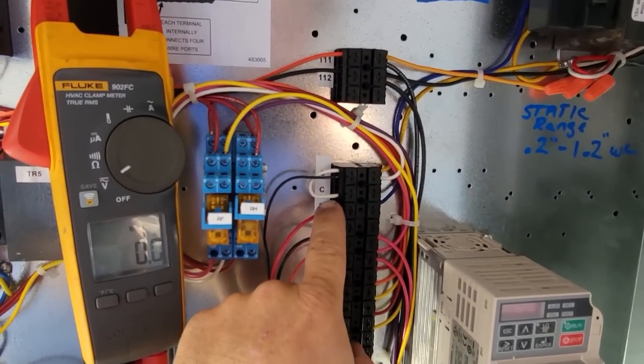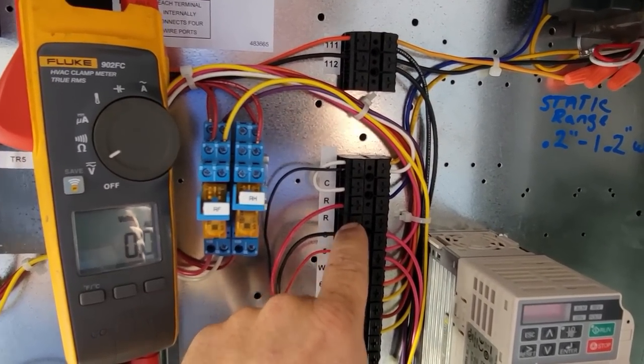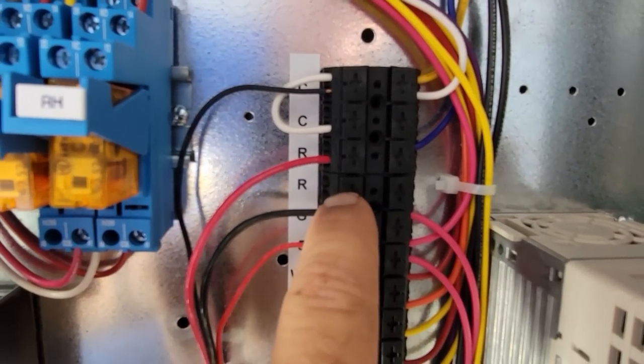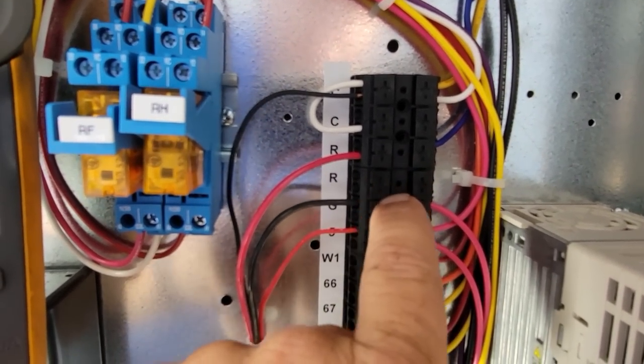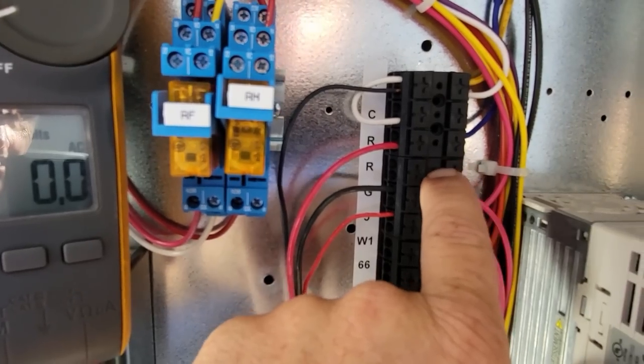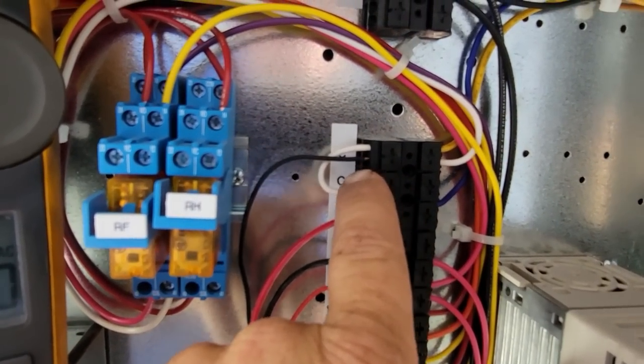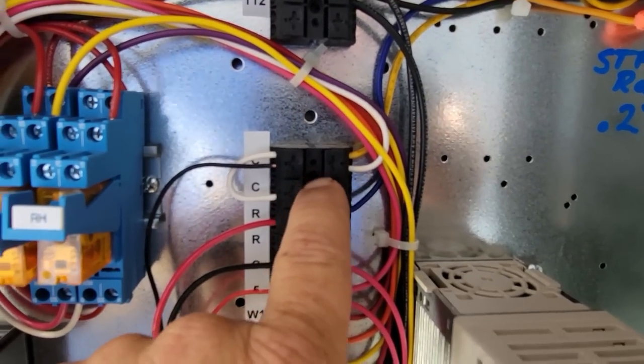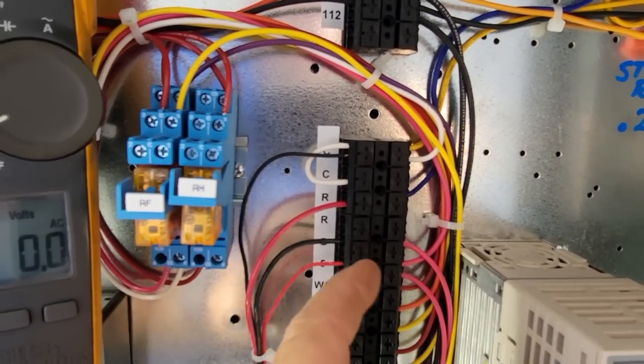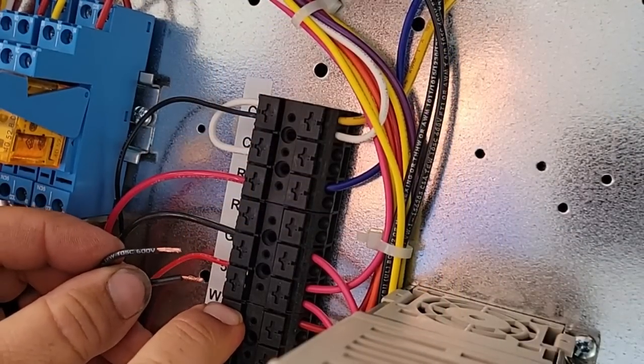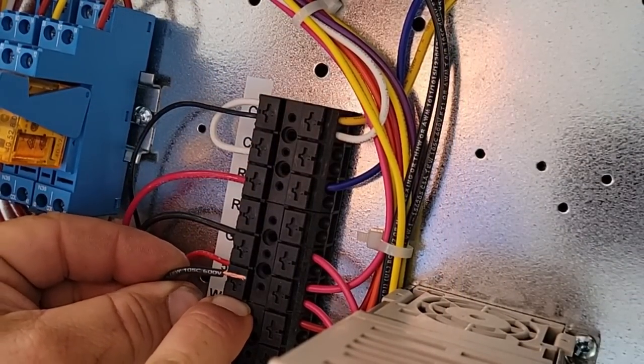So what we did here is we had a jumper between R and R. As you can tell, there's no wires in that particular R there. So I just took it out of there. Same thing with this common right here. See, there's no other common in there. You could even steal it from there. Gotta make sure you get them in nice and far, otherwise it won't hold there.